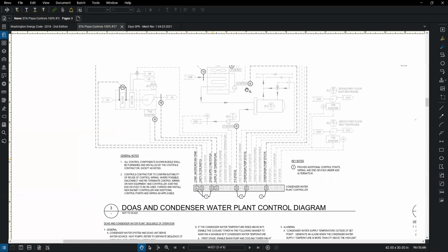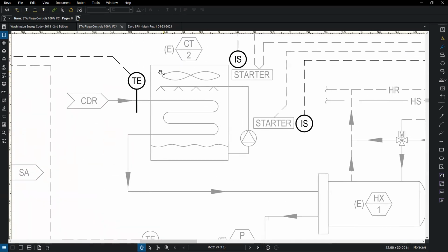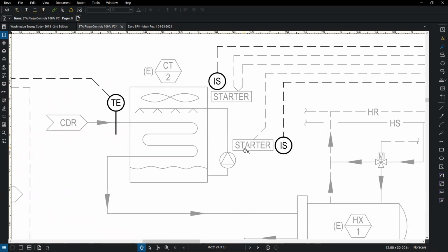We have a small DOAS unit and a condenser water plant. So we can see our cooling tower telling that basin pump when to turn on, also monitoring the status on the pump so we can tell when it's running, monitoring temperature.